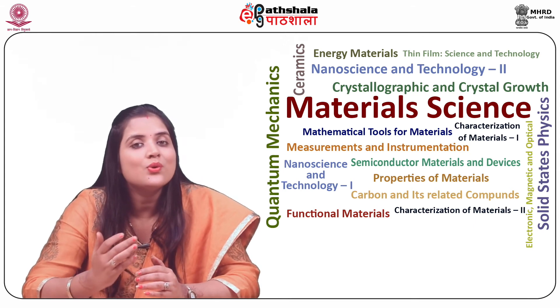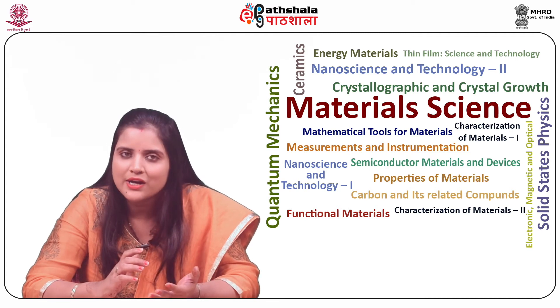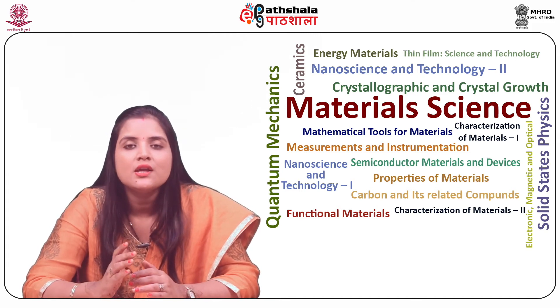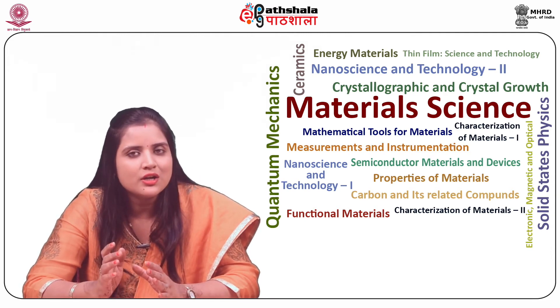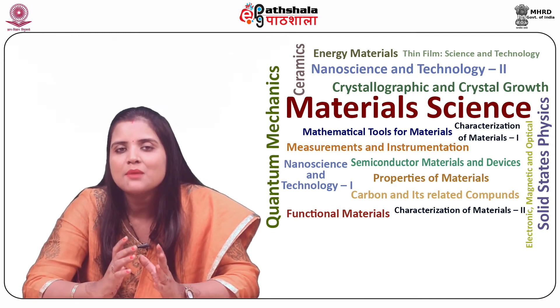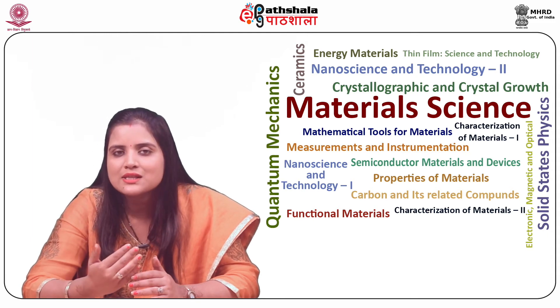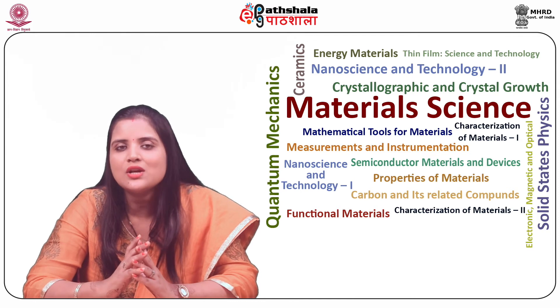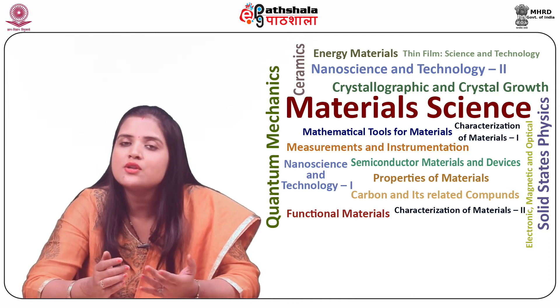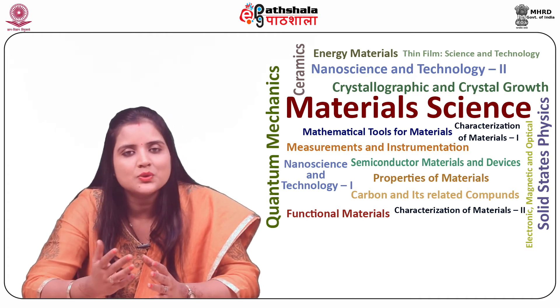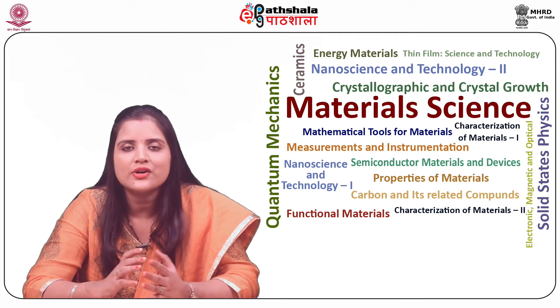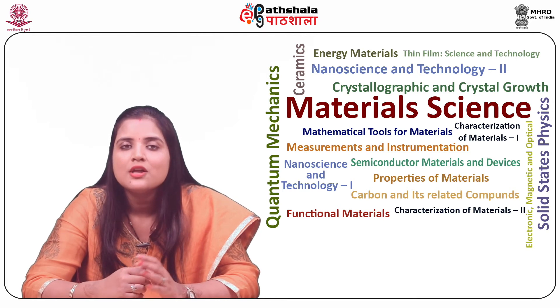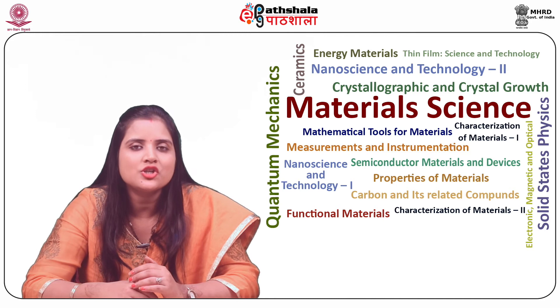Let us now discuss the source of illumination. The source of light used is a continuous 150-watt ozone-free xenon arc lamp. The lamp's light is accumulated by a diamond-turned elliptical-shaped mirror which is then focused onto the excitation monochromator entrance slit. A quartz-based window is used to isolate the excitation monochromator from the housing of the lamp, which shields against the unlikely occurrence of lamp failure.